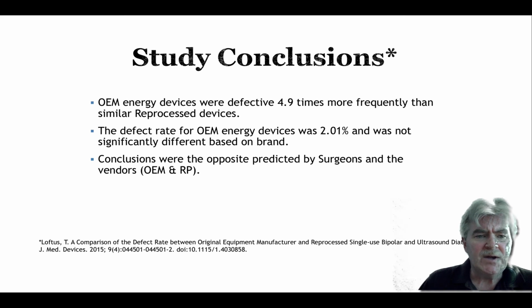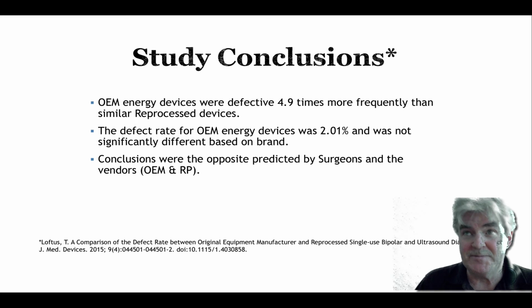So our conclusions were that OEM energy devices were defective 4.9 times more frequently than similar reprocessed devices. The defect rate for OEM energy devices was 2%, and was not significantly different based on brand. And the conclusions were the opposite of those predicted by the surgeons and the vendors, both the OEM and reprocessed vendors. Remember, surgeons said reprocessing was going to be worse. The OEM said surgeons said that reprocessing was going to be worse, that it would have a worse defect rate. The OEM said yes, the reprocessing will have a worse defect rate. And the reprocessing company said no, it will not be worse, it'll be equivalent. So they weren't even ready to go so far as to say that it might be superior, which gets back to some things with regards to how the FDA defines it. So it's kind of an interesting observation.